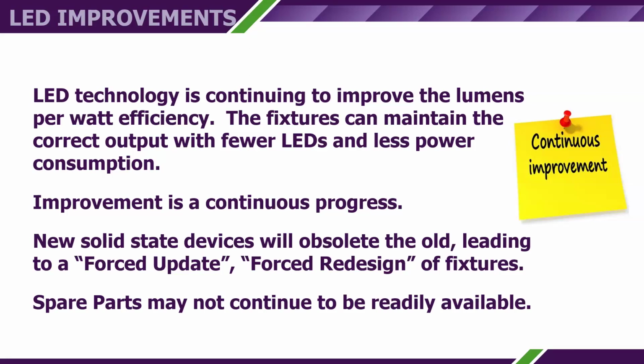Some of the manufacturers are being proactive with this. We had some issues with some taxiway centerline lights a decade ago, where the LEDs were being updated at such a fast rate that the manufacturers continuously had to redesign the power supply for the LEDs. So they designed what they referred to as a universal LED power supply, so that as the LEDs were updated, they would not have to change the LED power supply each and every time. So spare parts may not continue to always be readily available, just like the lamps not being available and the sockets not being available. You may not be able to get a diode or a power supply for your unit. One of the manufacturers explained to me like this: they're not truly manufacturers, they're assemblers.